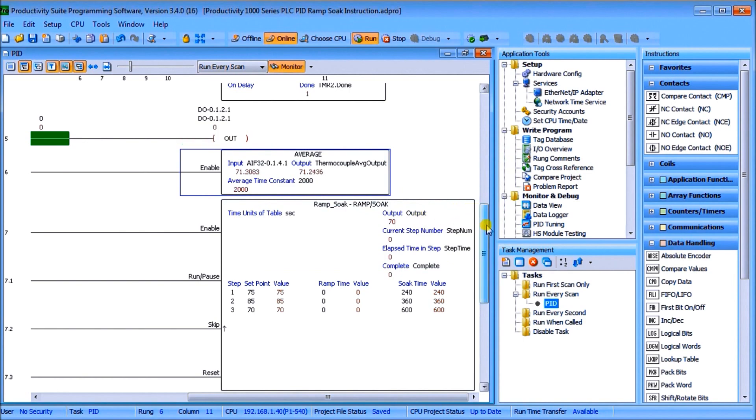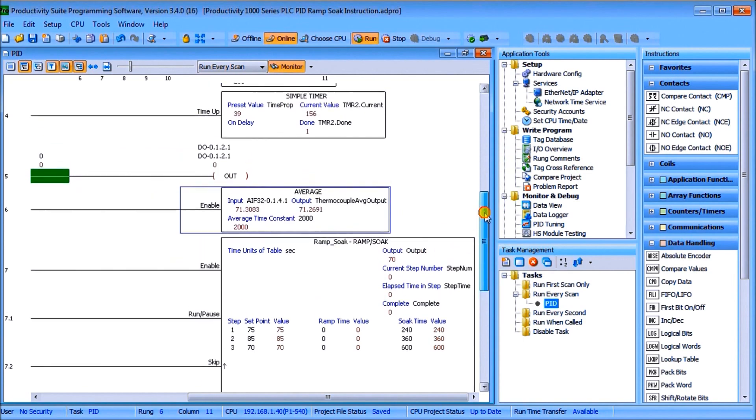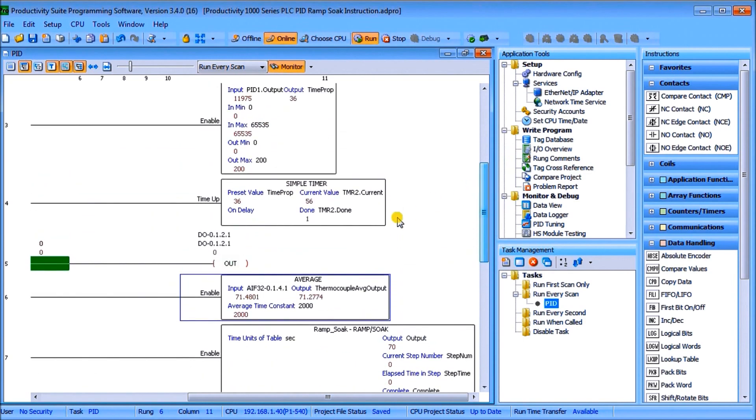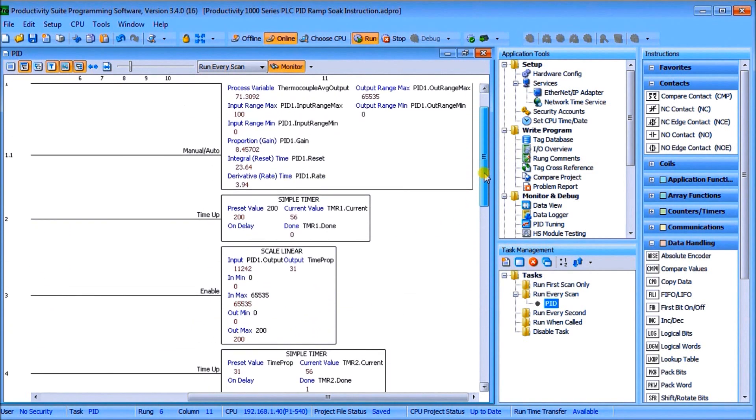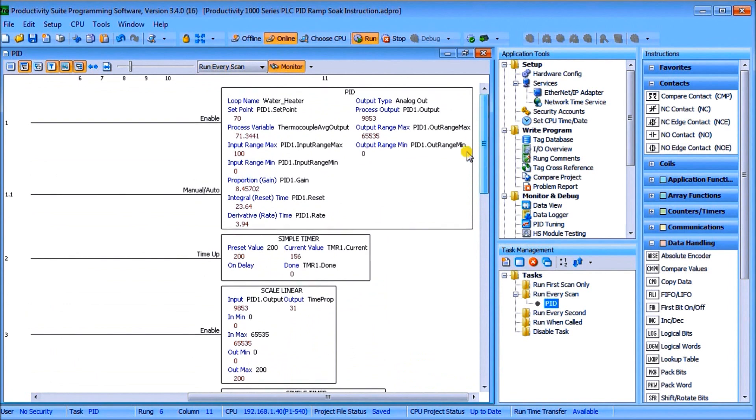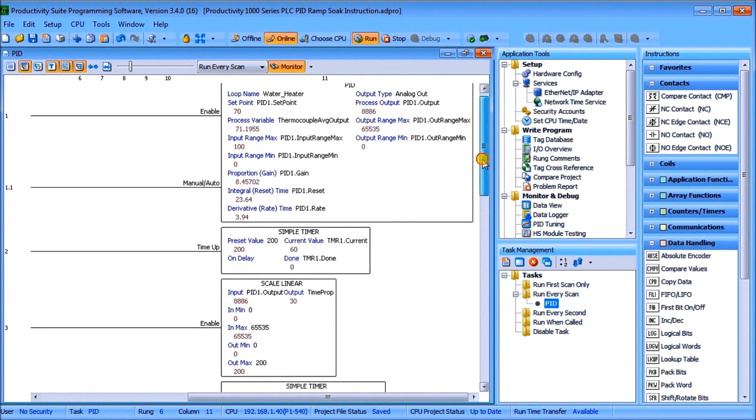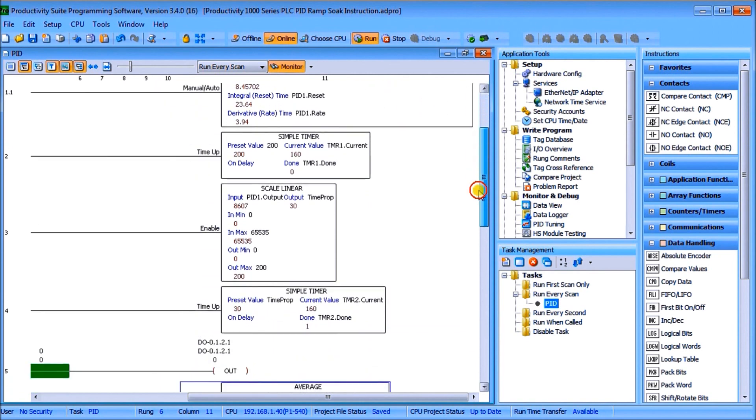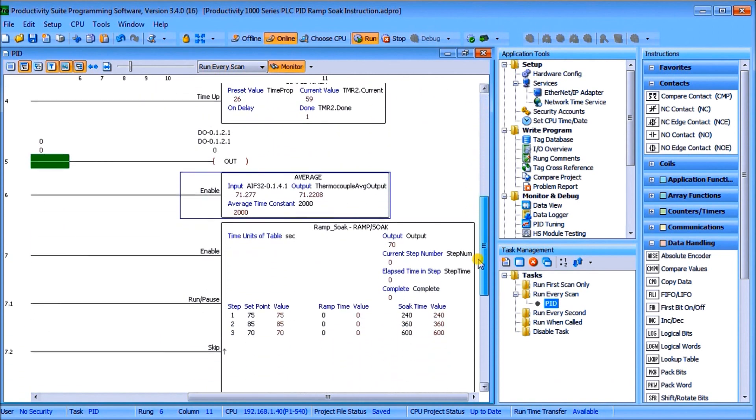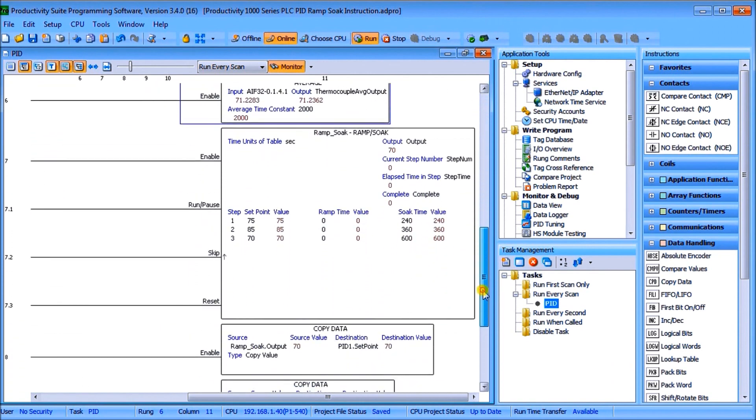So you'll see that we took that thermocouple average output and we actually applied it into our thermocouple average output for our process variable going into the PID controller, just to stabilize our PID a little bit more.